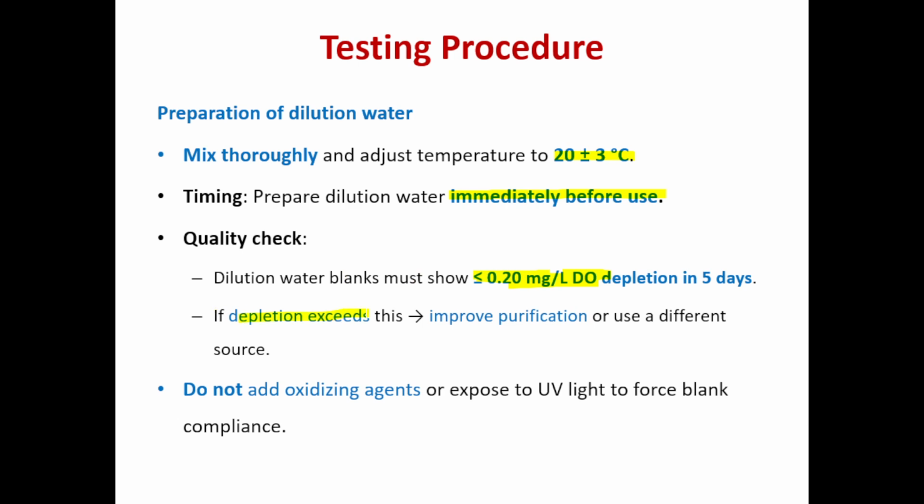If the depletion exceeds this, we need to improve the purification of this dilution water, or we need to use a different source. Don't add any oxidizing agent or expose it to UV light to force blank compliance. So note, we should not add an oxidizing agent or expose this water to UV light to achieve this compliance, the compliance of 0.2 mg per liter.